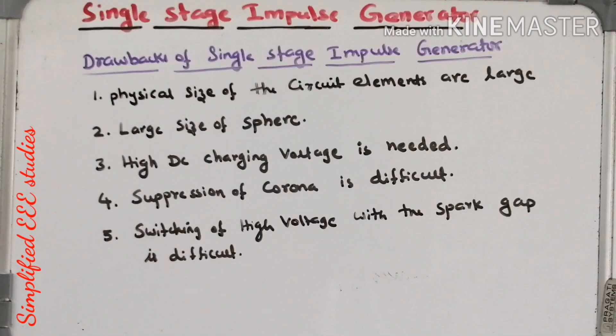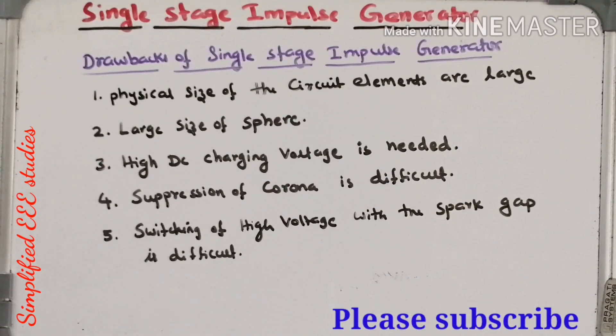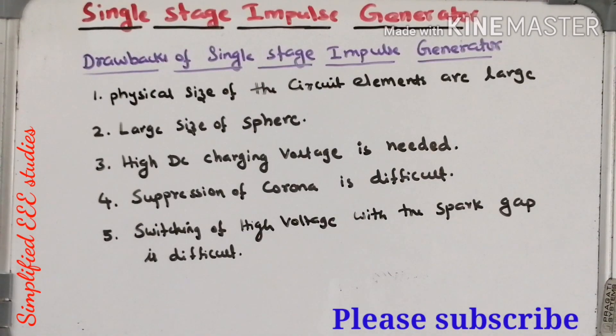The second drawback is that a large size sphere gap is required. The sphere gap acts as a switch, but we require a very large sphere gap which is totally undesirable. Third, a high DC charging input voltage is needed. Fourth, suppression of corona is difficult; it may cause errors and is a major difficulty. Fifth, switching of high voltage with the sphere gap is difficult.